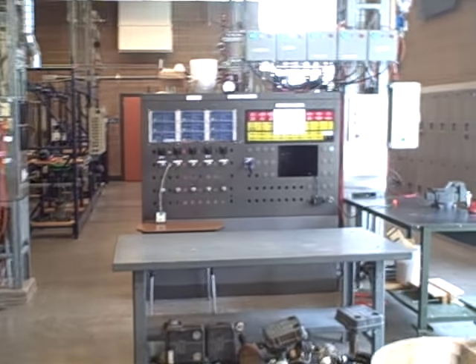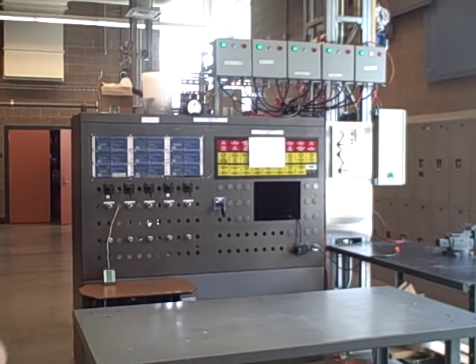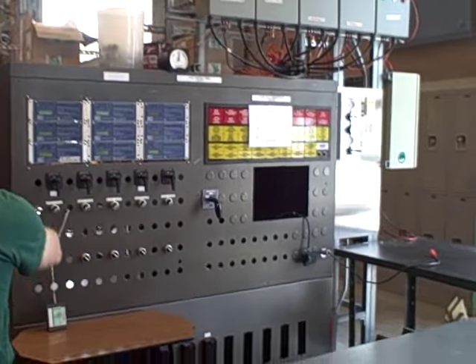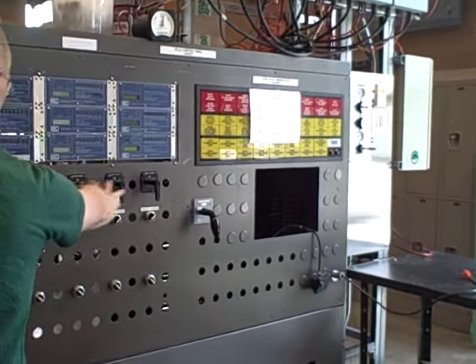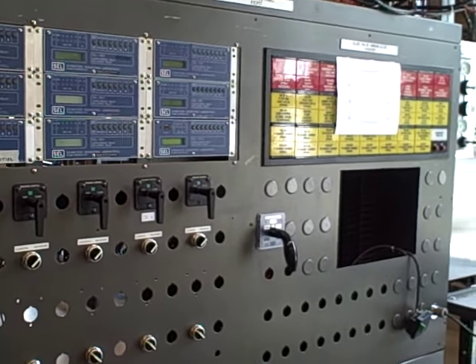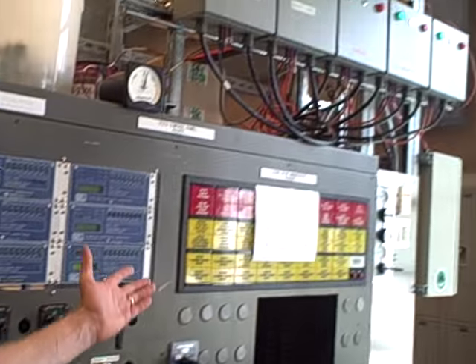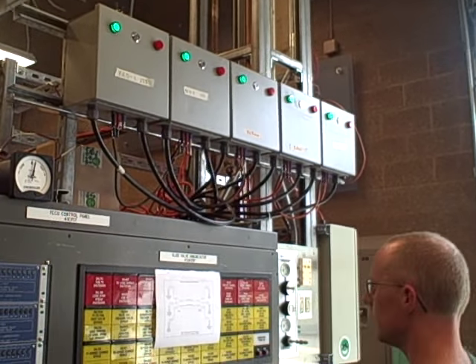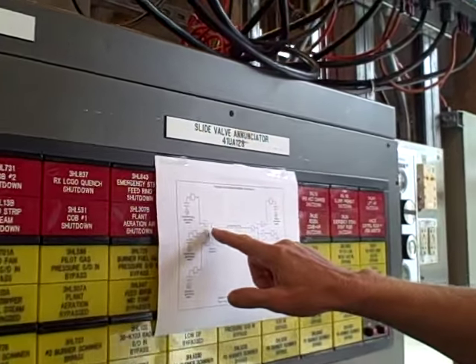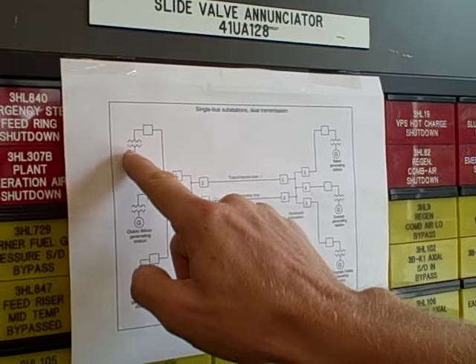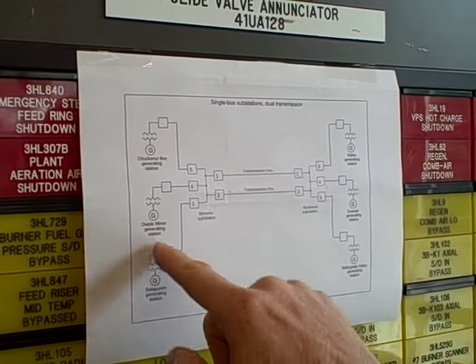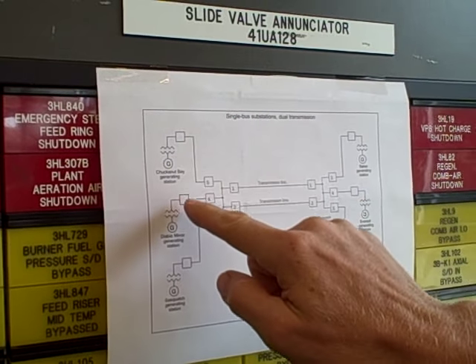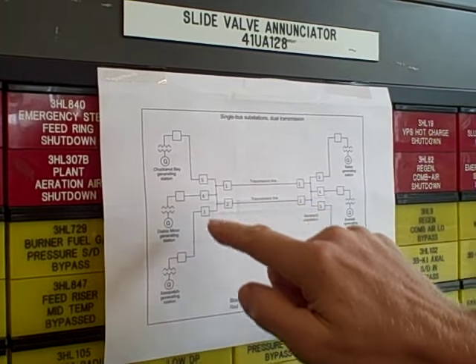We call this the Stevens substation. Different panel. Basically the same layout. We've got a selection of manual switches for trip and close breakers, and it is also reflected on the single line diagram. Breakers one through five. It's a single bus layout. So three generators with their own circuit breakers tie with connecting lines to the substation here.